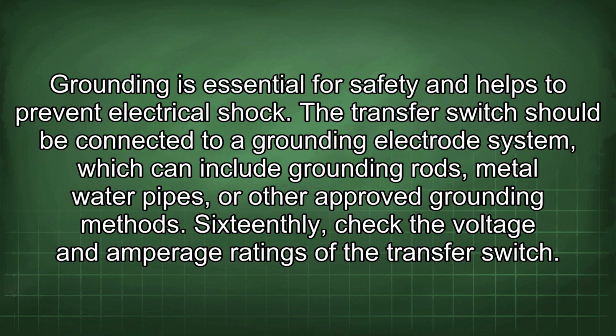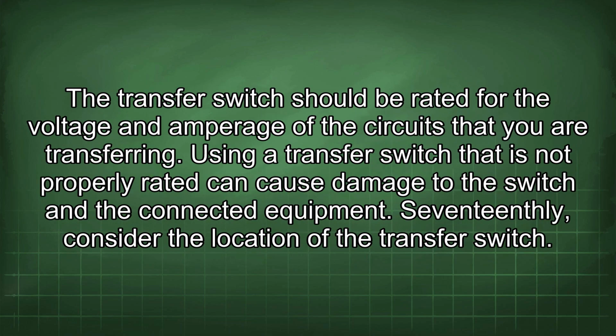16thly, check the voltage and amperage ratings of the transfer switch. The transfer switch should be rated for the voltage and amperage of the circuits that you are transferring. Using a transfer switch that is not properly rated can cause damage to the switch and the connected equipment.